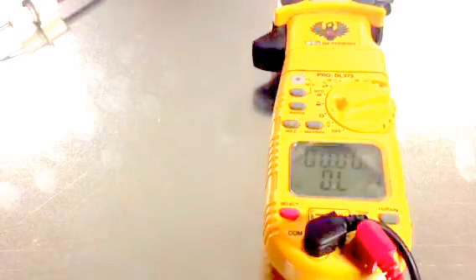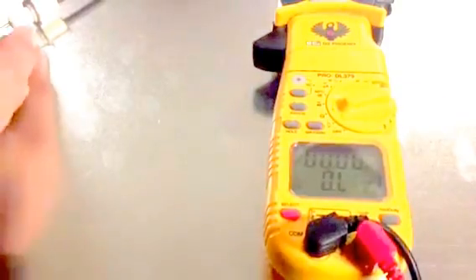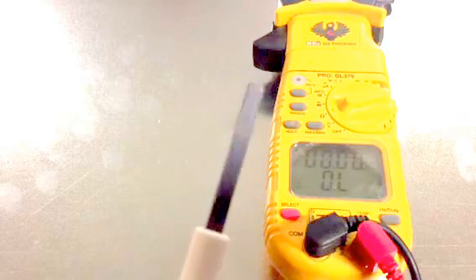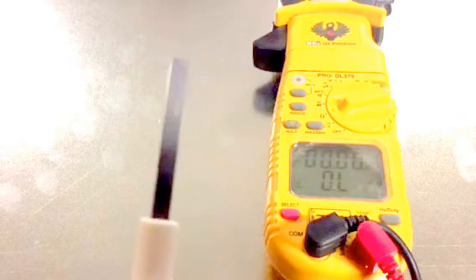Now it's best to check these when they're cool. You don't want them to heat - when they heat up that's going to change the ohms, change the resistance, so it's better that you give them time to cool off before you test them or test them before you fire off the furnace. So remember, carbide anything over a hundred recommend replacement, and just look for anything way over 11 to 18 on the nitride igniters. That's it.